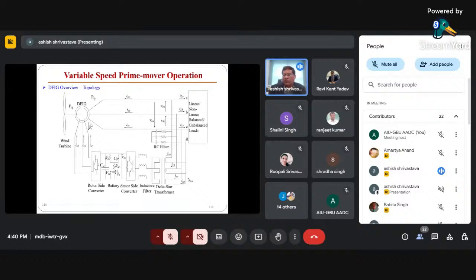Now coming to the last one, which is DFIG. In DFIG, there will be an isolated topology. So a delta and star transformer is there, and then you have a battery, and then you have a rotor side converter and a stator side converter. The rotor side converter is injecting into the rotor side, and the stator side converter would be requiring battery charging, or it is feeding back to the load. So depending upon the power flow, because in DFIG power can flow in either direction. That's the advantage of the DFIG topology. So this is one of the variable speed wind energy conversion systems with DFIG.